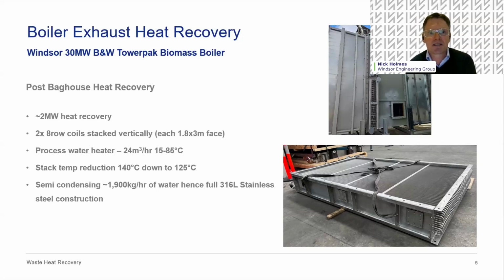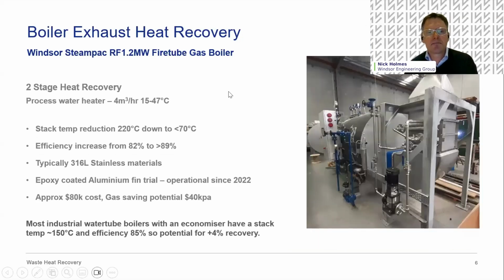This was a semi-condensing application. So burning biomass that's got a lot of water in it, the water passes through the boiler and it's water vapor that's then passing through the stack. So if we can utilize some of that latent heat, you get extra bang for your buck in terms of condensing that water out and recovering the energy. So that's at the sort of large end of what we can do with heat recovery. The same technology at a much smaller scale.